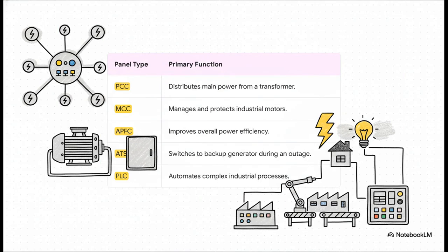And from there, the specialization gets incredibly precise. Take a motor control center, an MCC. That's absolutely essential in a factory because the huge burst of current it takes to start a giant motor would trip a normal breaker instantly. Or an ATS panel, a literal lifesaver in a hospital because it instantly switches to backup generator power during an outage. And a PLC panel, that's the sophisticated brain behind complex automation, coordinating hundreds of processes at once.